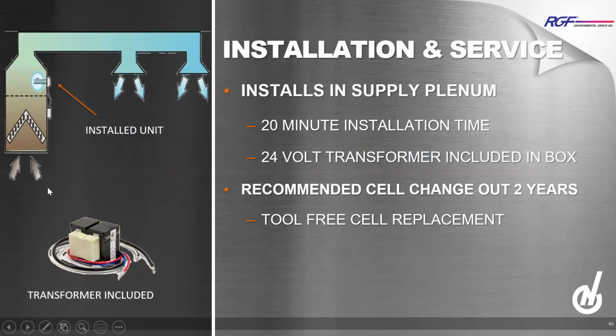A common question I get is, can it be installed upstream of the A-coil? It can, but it's not the ideal placement because you lose some of the PHI to the coil, though it will keep your coil clean. You lose some of that PHI that would otherwise go into the occupied space, so we prefer installing it on the downstream side.